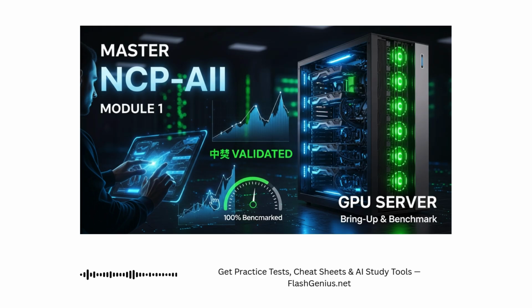Okay, let's wrap up this section with topic 1.5. Power and cooling validation. No matter how perfect your fabric is, if the system overheats or runs out of power, the whole AI factory just shuts down. These servers demand huge amounts of sustained power. A DGX A100 can pull 6 to 7 kilowatts. It generates a ton of heat. So validation here is all about preventing 2 things: thermal throttling, which silently kills your performance, and sudden circuit trips, which cause downtime. So let's start with power validation.